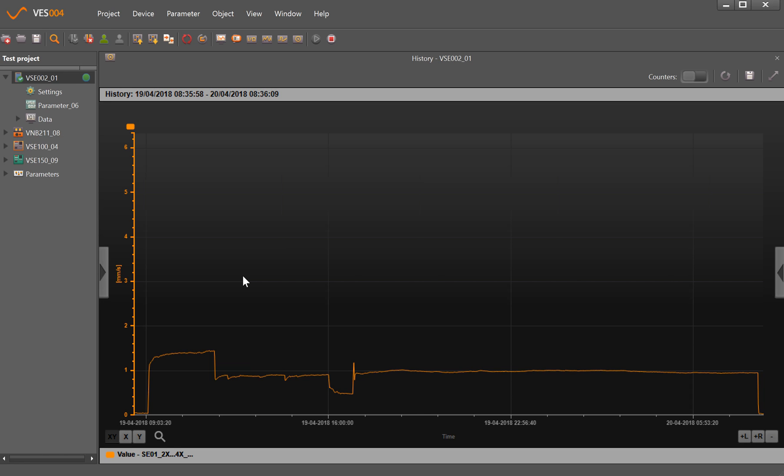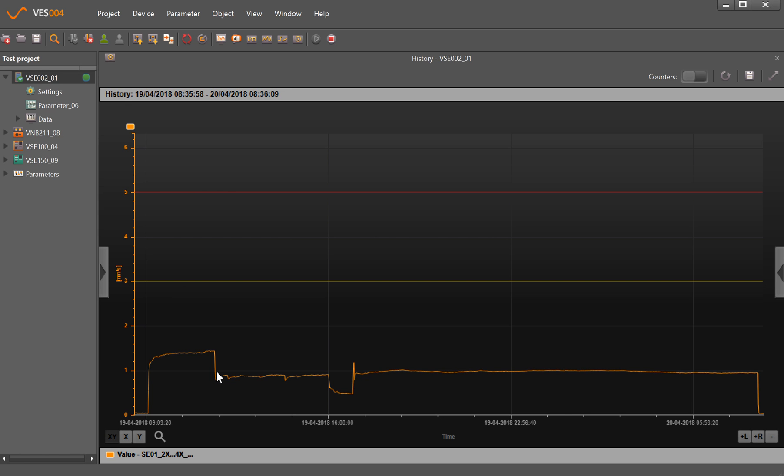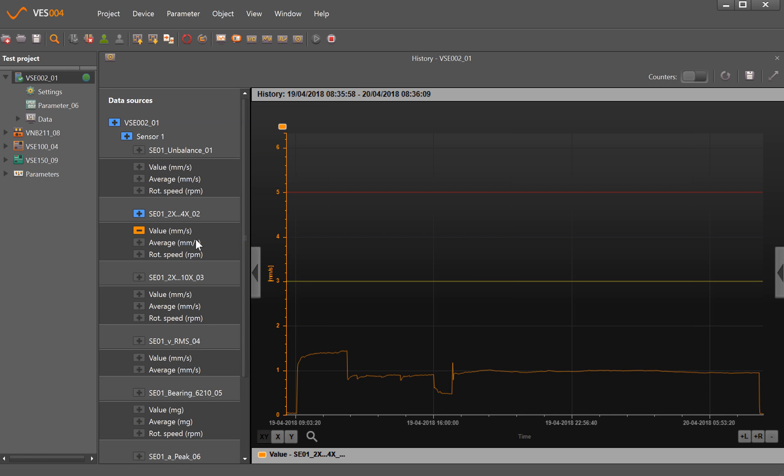So now looking at the history trend that was gathered, this is just from a small fan system I have in the office here, so the levels being detected are much lower than you would normally get on normal industrial machinery. This has given me a trend overnight basically. You can see the millimeters per second levels up the left here. If I want to show where the alarm limits are, if I just left-click on the rectangle there, that puts them in. We can see that we've got a yellow alarm at 3 millimeters per second and a red at 5 millimeters per second. There was a little bit of change at the start of the history trend but that's kind of settled down, and you can see for much of it it's basically leveled off at 1 millimeter per second. We have an alarm set at 3 and 5, so I'd be quite happy to keep those alarm limits where they are for that one.